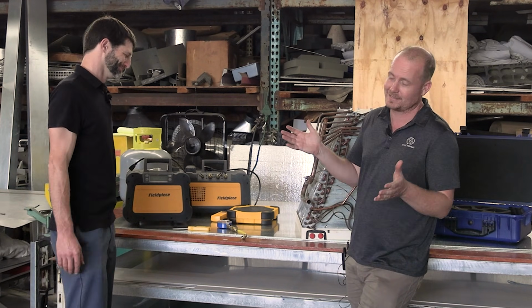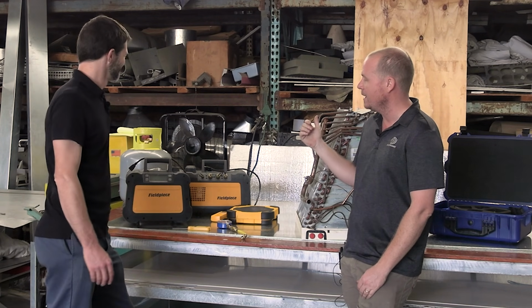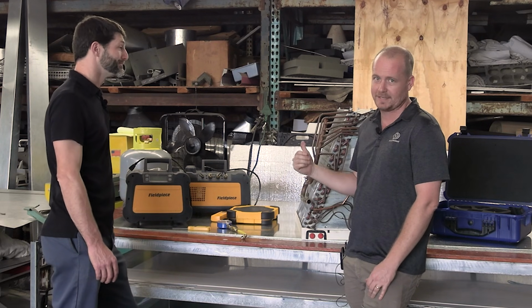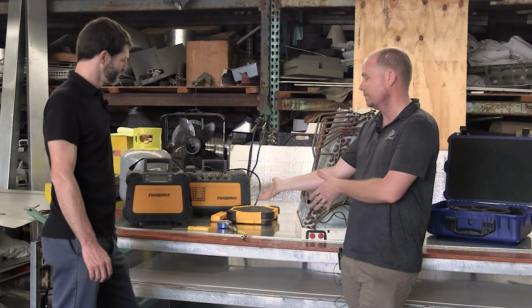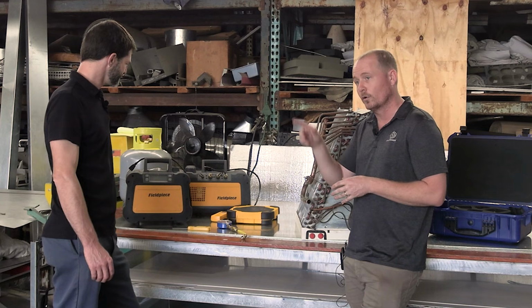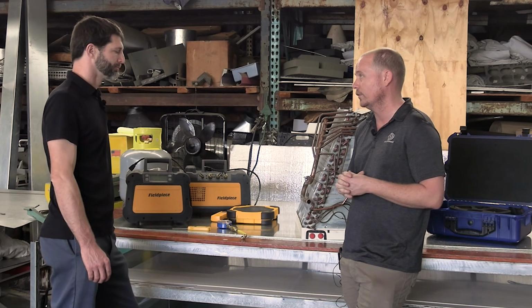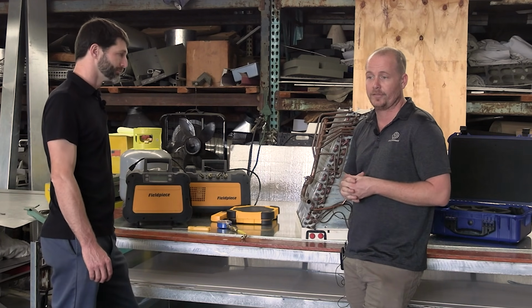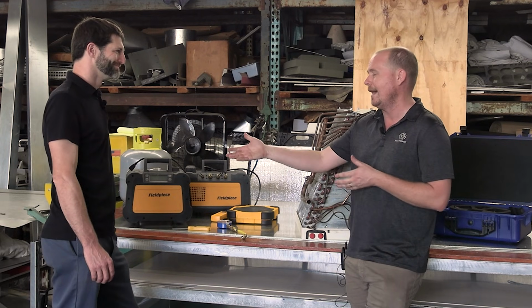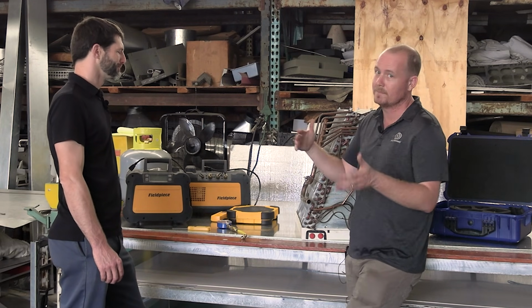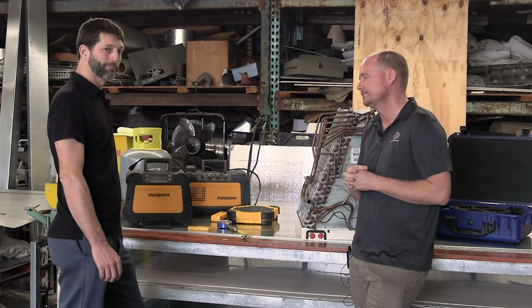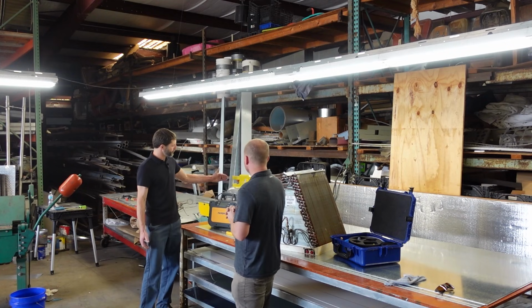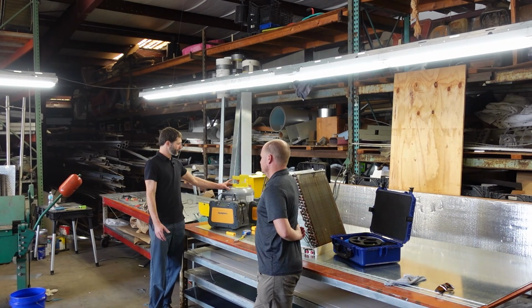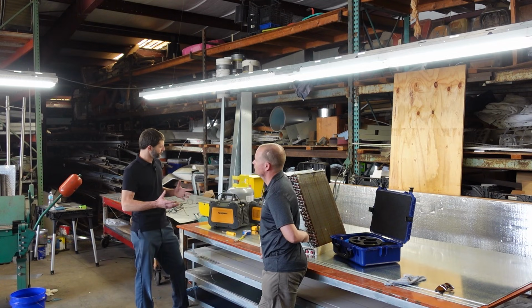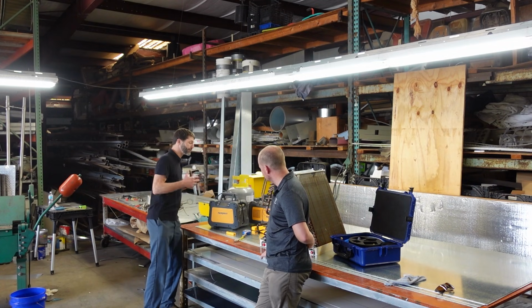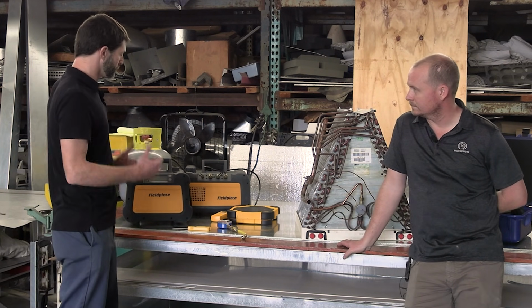But either way, that's probably an assumption on my part. But hopefully you know what's in the tank, or what's supposed to be in the tank, and then you can compare that to your PT chart or to the saturated curve on your gauge in order to make sure that you're not going to, again, have more work than you need, and then also not mixing refrigerants. That's also really important. So if this is in your shop, you really want to make sure that it hasn't moved its location, and the temperature surrounding this tank should be steady for several hours in order to do that.